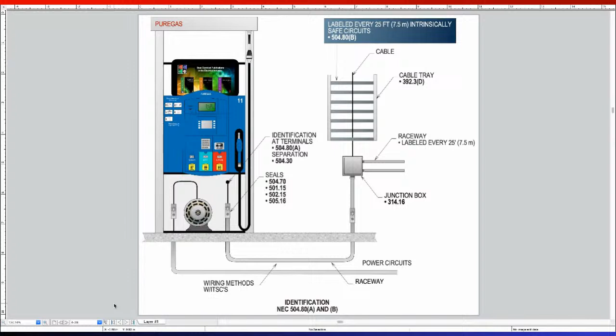When we get over there, we'll get into Article 511 and 514—one deals with gasoline stations, the other with service areas. We go in and talk about how far out is considered the classified location, and explain all of that. But when dealing with a hazardous location area not defined in a specific article of the National Electrical Code, there are other things to consider, like pressure in the raceways, or tubing, where they've made all their connections for the sensing devices.